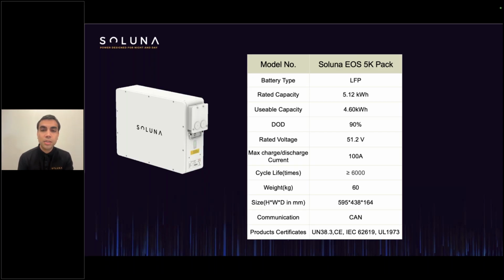It is 1C rated, which means that you can charge and discharge within an hour. And the life cycle is 6,000 cycles. If you have, let's say, a discharge and a charge once a day, you can have a battery for 16 years. The weight is 60 kilograms. In millimeters, the height is 595 millimeters. The width is 438, and the depth is 164 millimeters. We use CAN communication and Wi-Fi communication, and it's certified UL 1973.